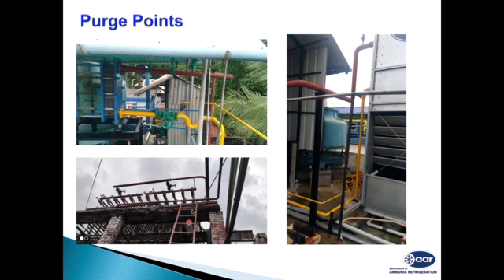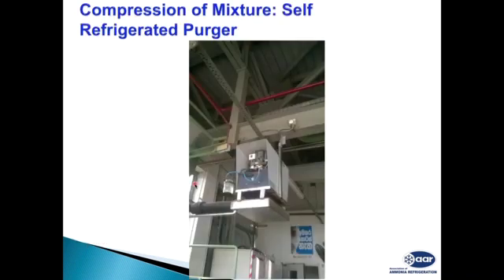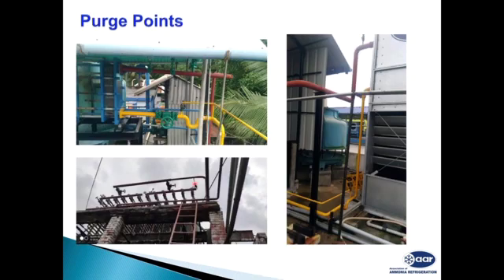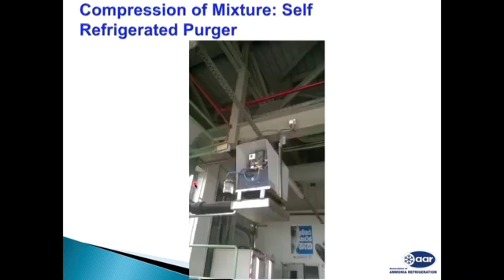In our cold storages, many times we use atmospheric condensers. We can install an air purger on atmospheric condensers also. You can see here this header is connected for the condensers, and the purge point is taken from this place on the header. So these are the different purge points we can connect. Always remember, the success of an air purger depends on proper purge point connections. This is a photograph of a compression-based unit. You can see this unit is installed on the top, and this piping is connected at the bottom on the receiver. These are the receiver points, and this has an inbuilt compressor and monitoring unit.